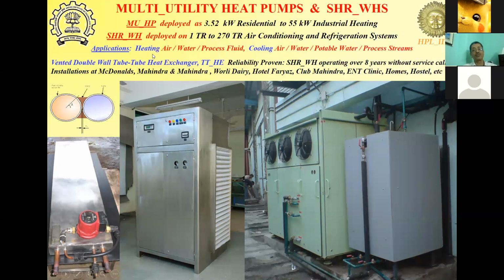What do they cater to? They can cater to heating, that is air heating, water heating, process fluid heating directly. Normally, conventional heat pumps heat up clean fluid, and then the clean fluid is used to heat up the process fluid because of the worry about contamination or accidental mixing of the two fluids. In this case, because of the reliable tube-tube heat exchanger, which in its simplest form could be something like 2 tubes put side by side and thermally bonded with a thermal bonding material.